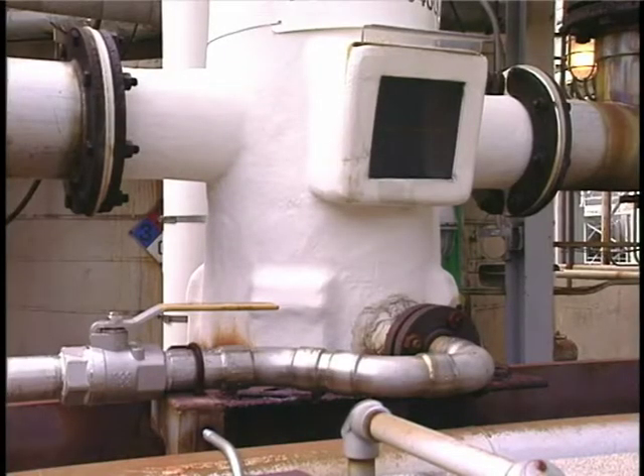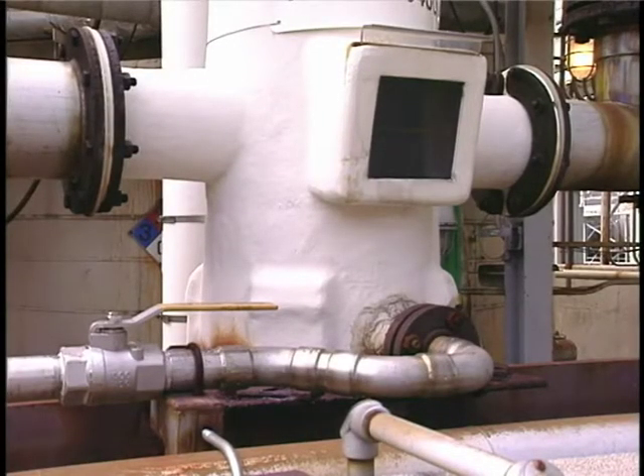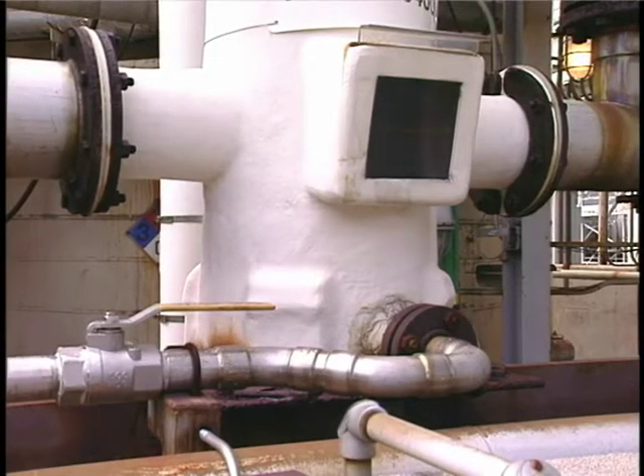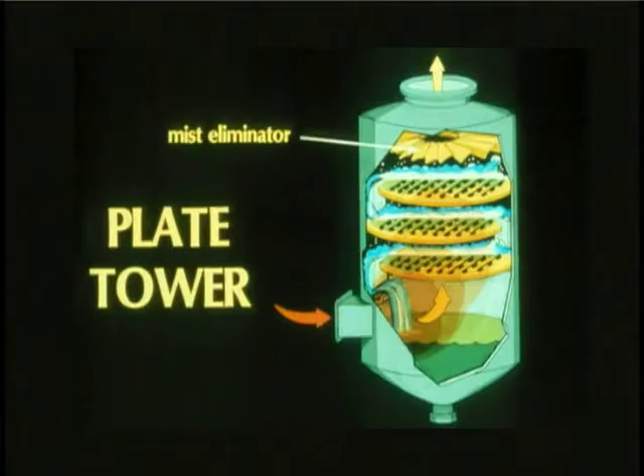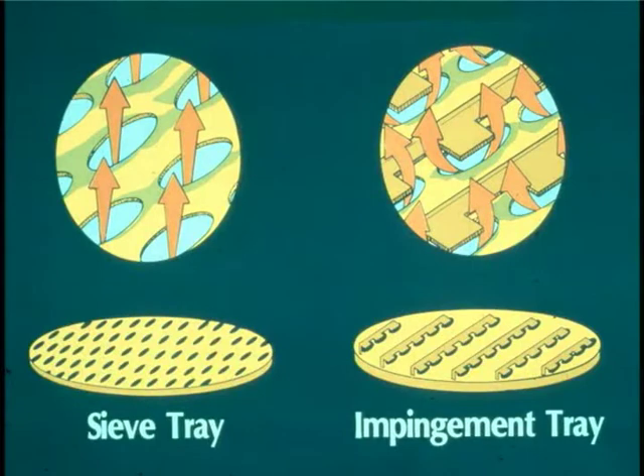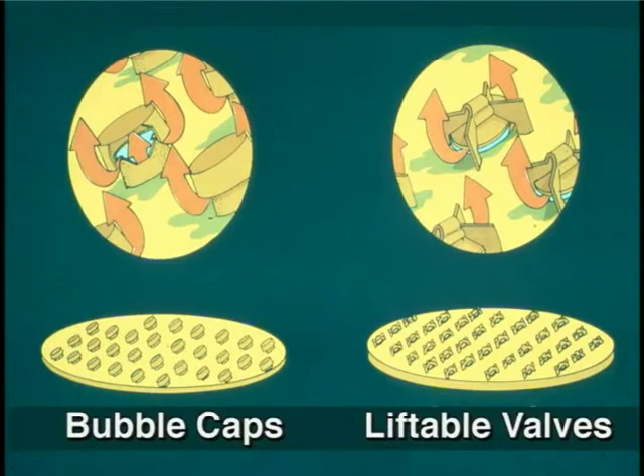Tray scrubbers are vulnerable to solids accumulation and plugging problems. Regardless of the tray design, all of these units operate in a similar manner. The contaminated gas stream enters at the bottom and flows upward through the holes in the plates. The liquid enters at the top of the tower, flows across the tray and then through a downcomer to the tray below until it reaches the bottom of the tower. The function of the trays is to disperse the liquid into droplets and the gas stream into bubbles, creating the gas-liquid contact necessary for particle collection.